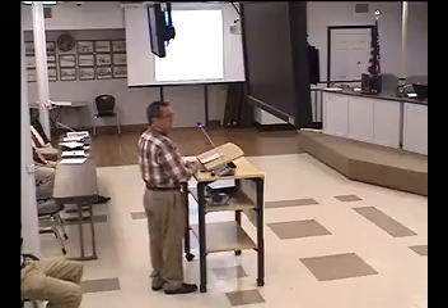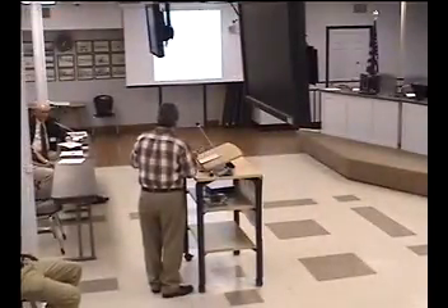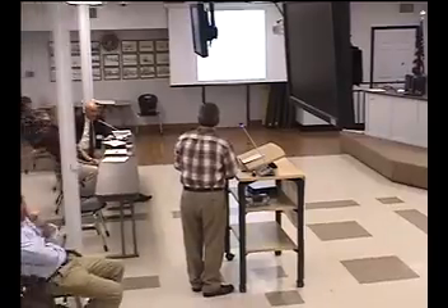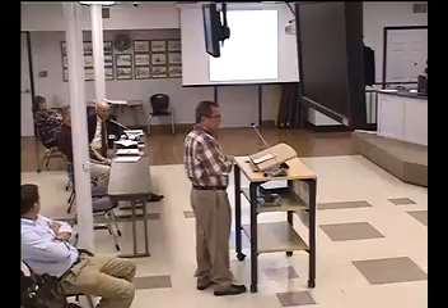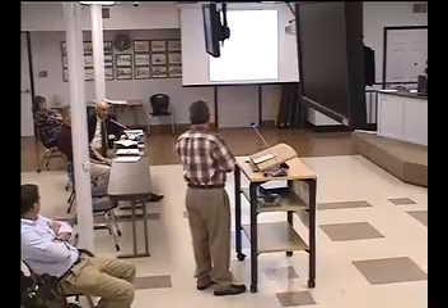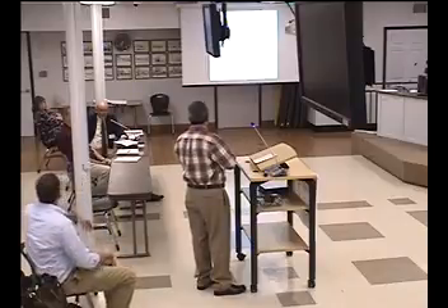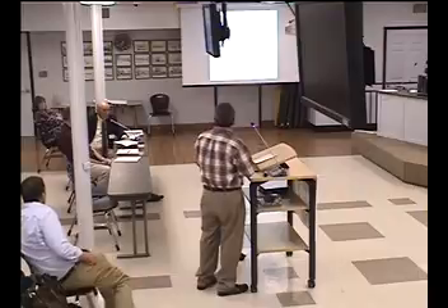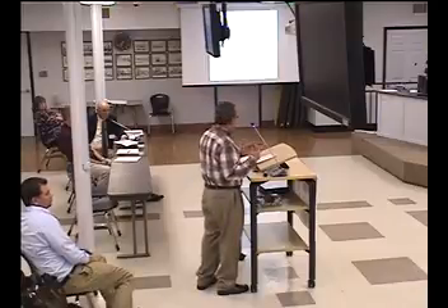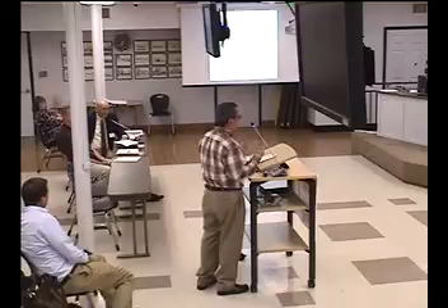You may have just answered it — so you think if we go this $75,000 route and just do the unit on the roof, we could possibly get 2 years? I think so — I don't have any reason to say no. The boilers are in relatively good shape; I think we've actually replaced the boiler. It's not the original boiler — we replaced it several years ago, so it's got some age on it, but it's not original. I can't speak to the exact condition of those units in the classrooms — there may be some that aren't working, but I don't know that for sure. We can't say you won't have some issues you have to fix, but I think you could get a couple years out of it.